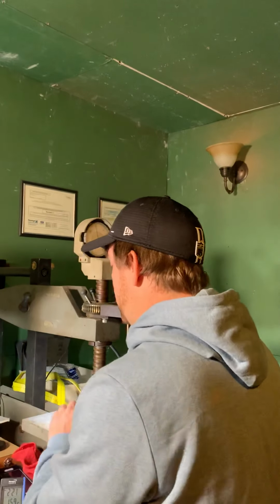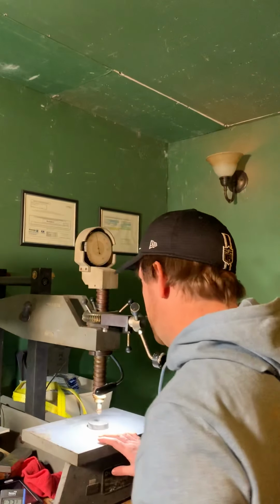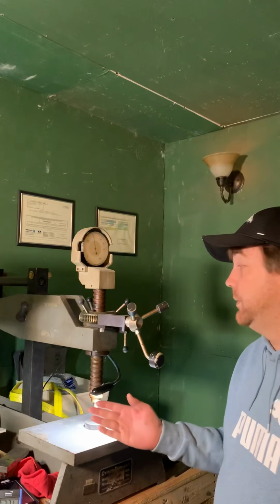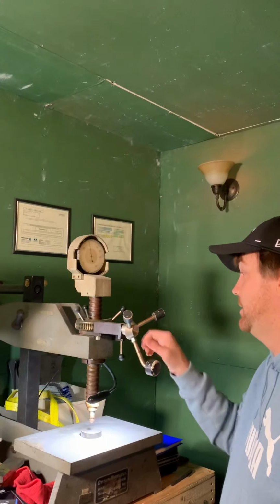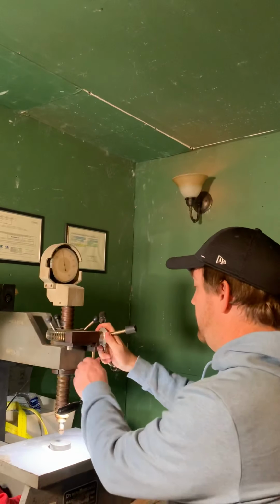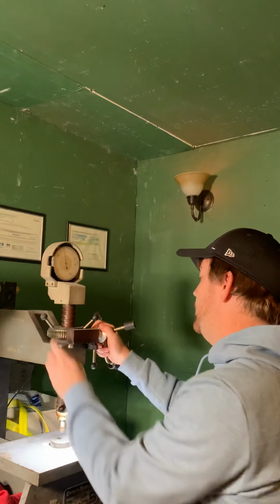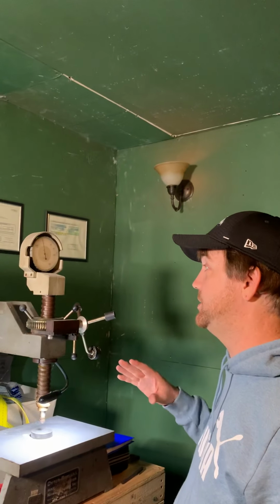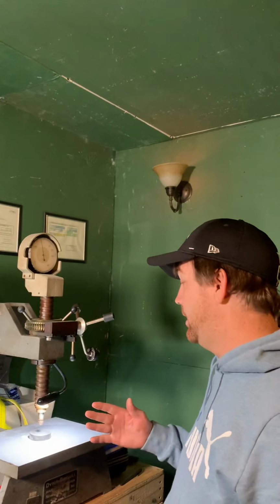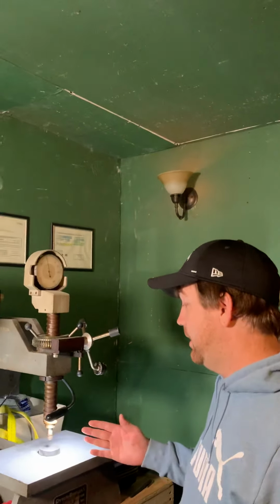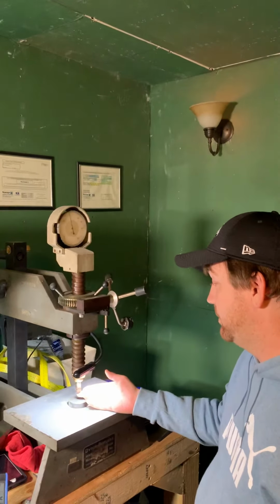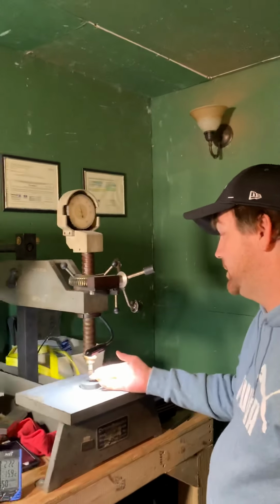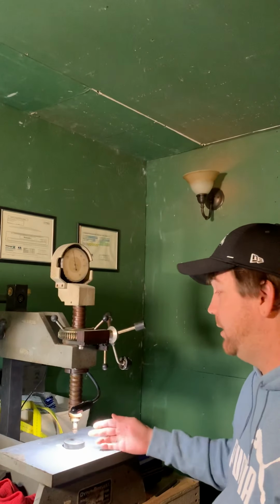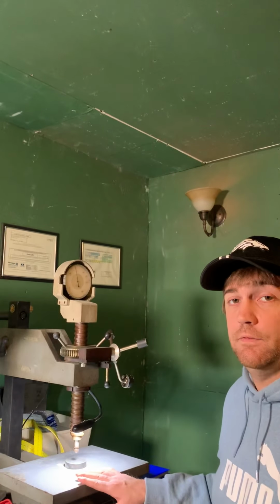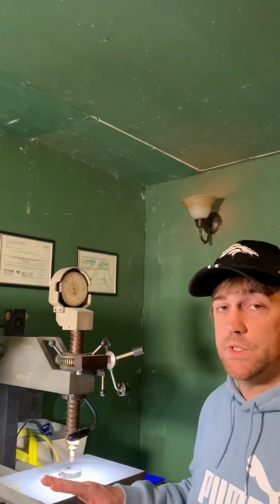Now, after you measure your as found readings, you do the same thing as you did for the Rockwell. You perform any maintenance that is suggested in the manual for that particular piece of equipment, as well as any calibrations that need to be performed either to bring the tester closer to nominal or bring it within tolerance. After you've performed anything like that, and also checked the ball penetrator as well as any other components which are subject to wear, after that's done, you take your final readings with the same 2 blocks.